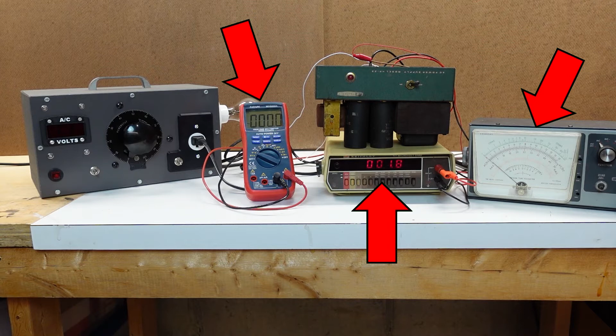Anytime I'm doing testing with AC voltages, I'm using my dim bulb tester, which I've featured in several episodes. If you're not familiar with it, it has an isolation transformer and an auto transformer, so I can vary the voltage. As I always say, I'm looking for that light bulb in the back to not glow. I need to move the meter over a bit so we can see the filament better.